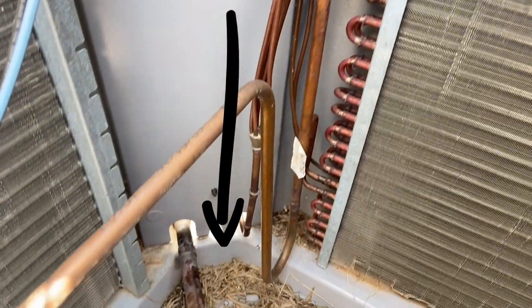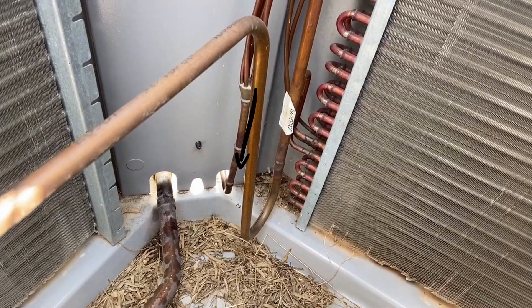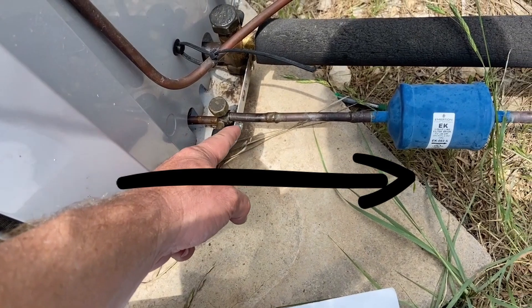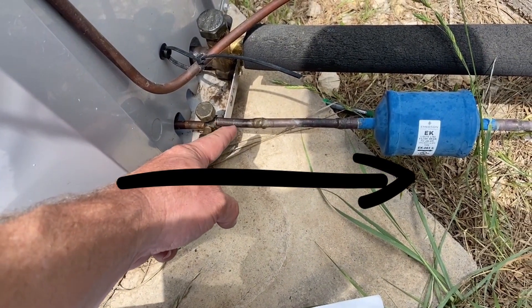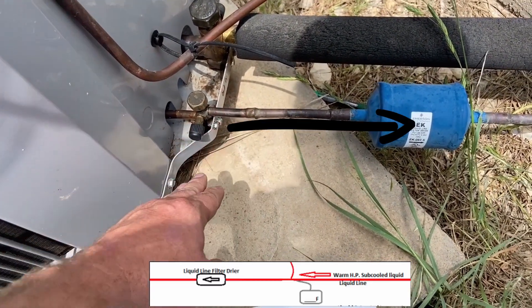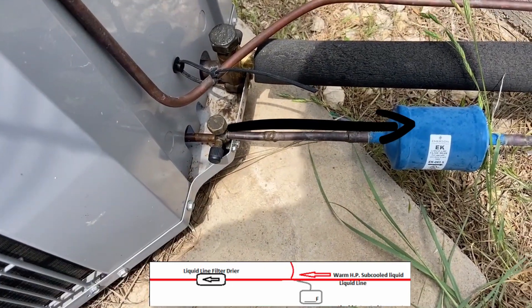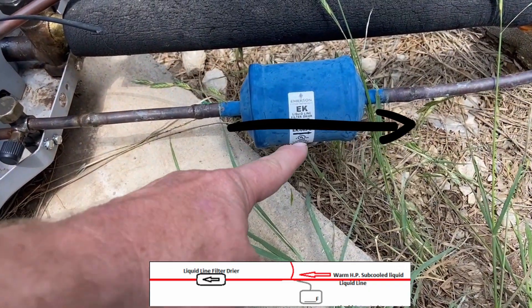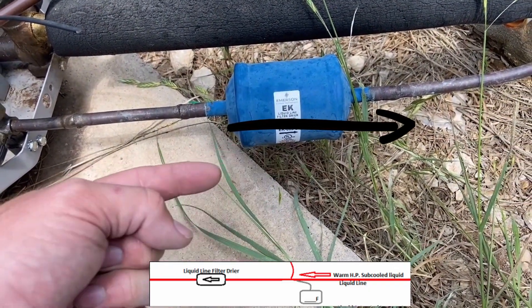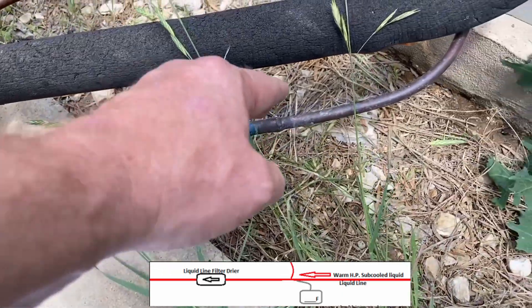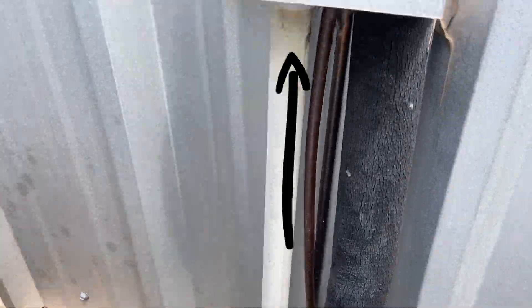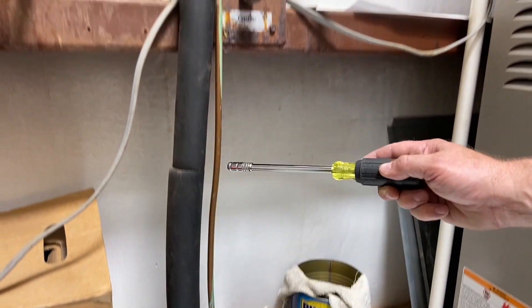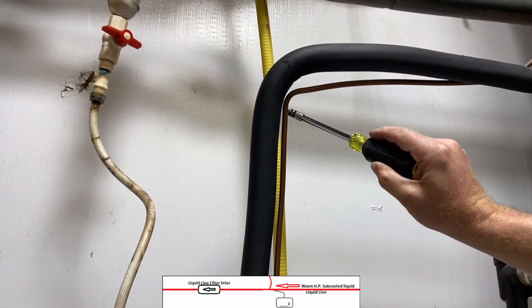The refrigerant leaves through the liquid line going outside of the unit. This liquid line is 100% liquid — it is a subcooled liquid. If I touch it, it's going to be warm to my touch, but the refrigerant is subcooled below its saturation temperature. We go into our liquid line filter dryer — you can see there's an arrow pointing away from the unit towards the inside — and continue with our liquid line into the building.